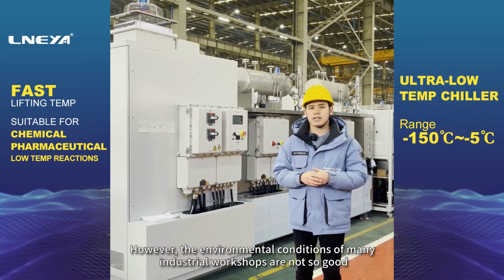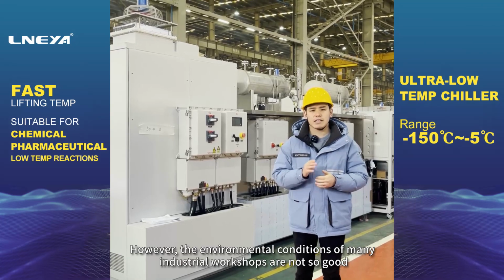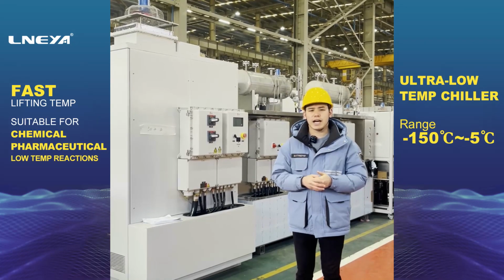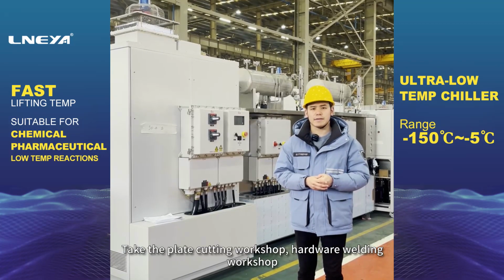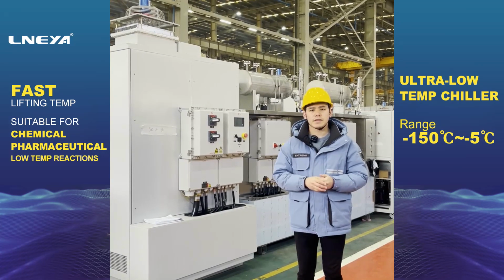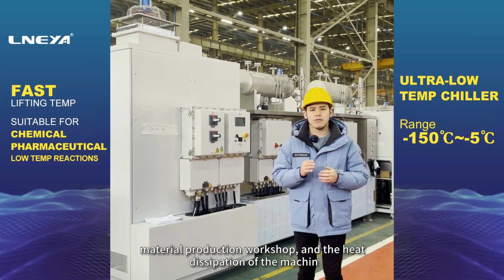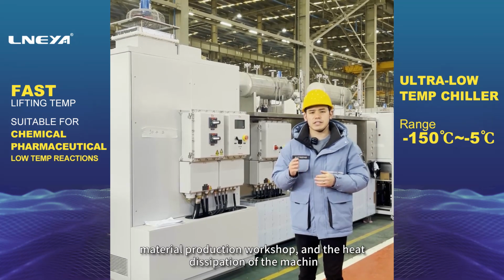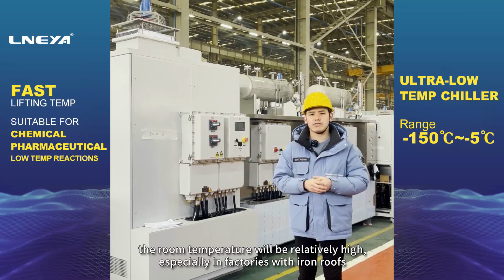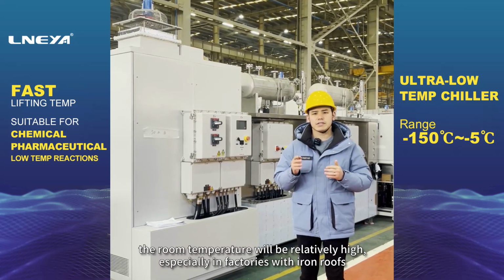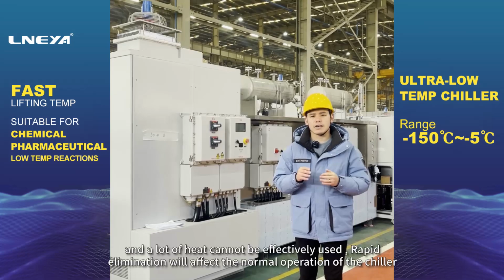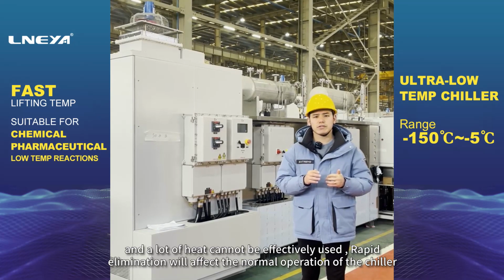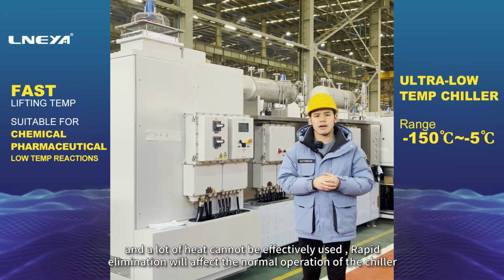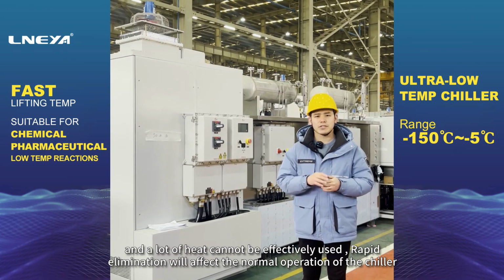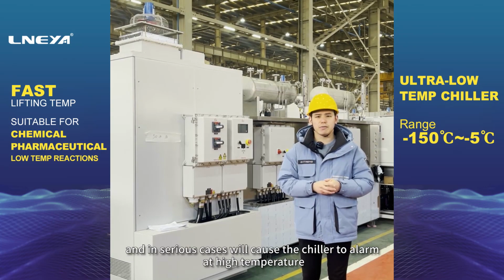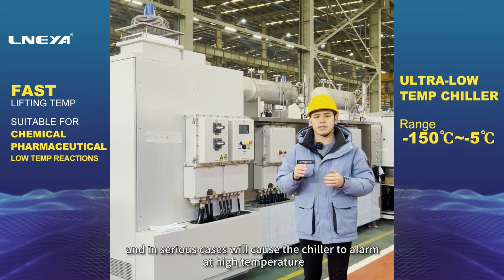However, the environmental conditions of many industrial workshops are not so good. Take the plate cutting workshop, hardware welding workshop, material production workshop, and machine heat dissipation as examples - the room temperature will be relatively high, especially in factories with iron roofs, where a lot of heat cannot be effectively dissipated. This will affect the normal operation of the chiller, and in serious cases will cause the chiller to alarm at high temperature.